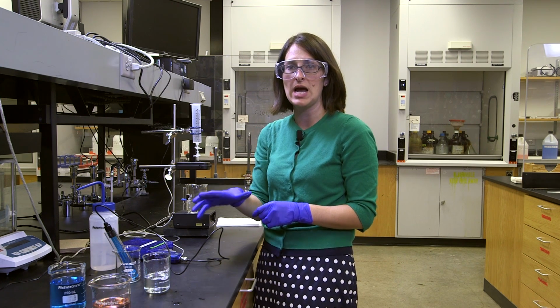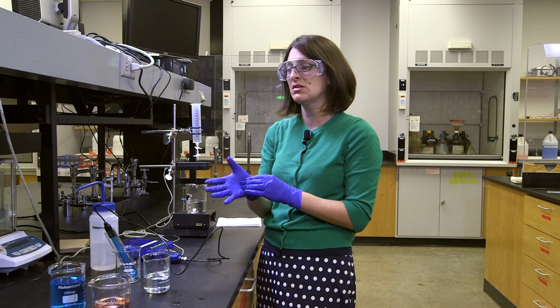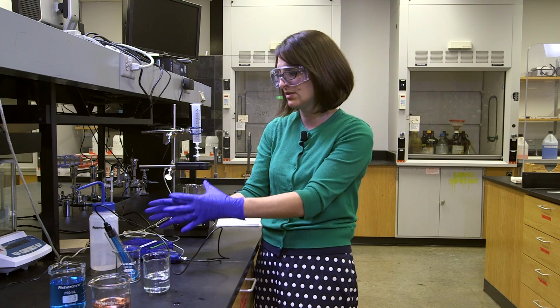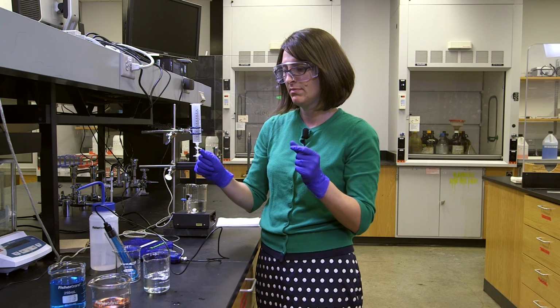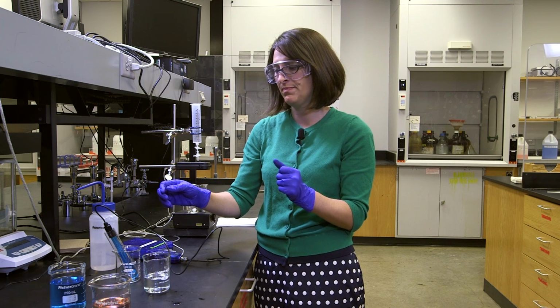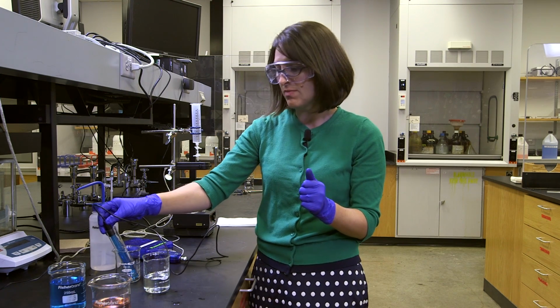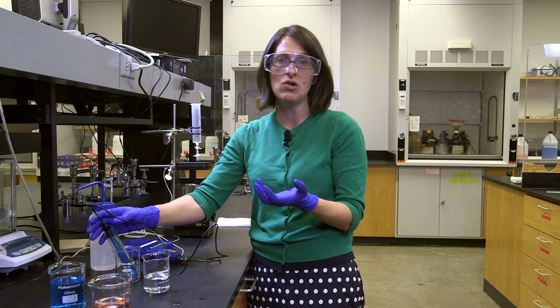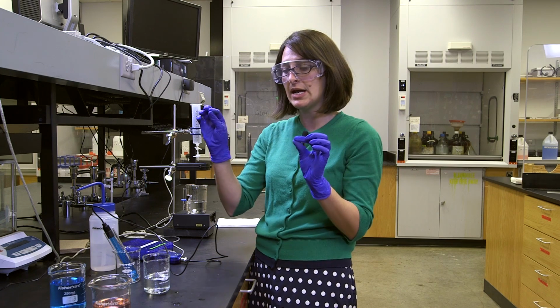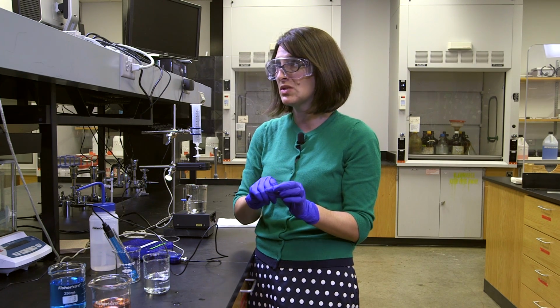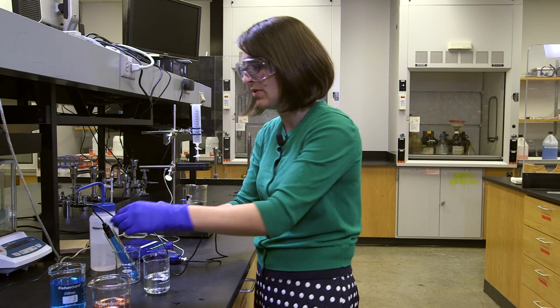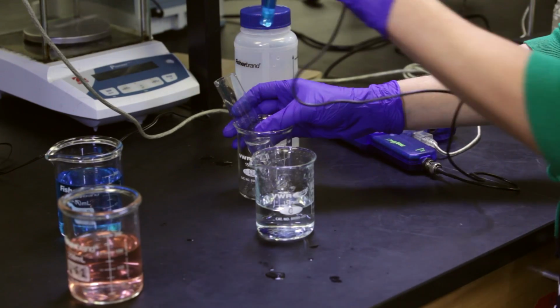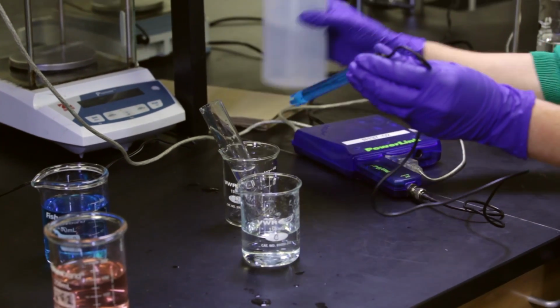So if you've worked in a lab that uses a pH meter, this is a little bit different because we have to tell the computer how to do everything instead of just using the base of the pH meter. Before I start my readings, I have to calibrate. I have to tell the computer my low pH and a high pH. So those two data points will create a line, and all of those subsequent readings will be based off of those two points. So I want to take out my pH probe and I want to rinse it off.